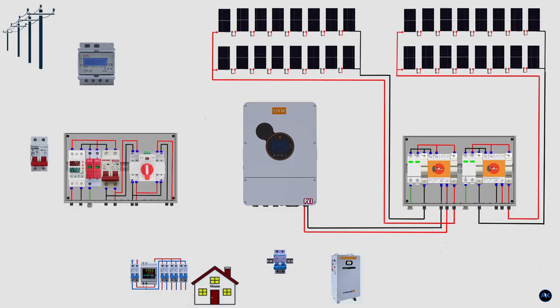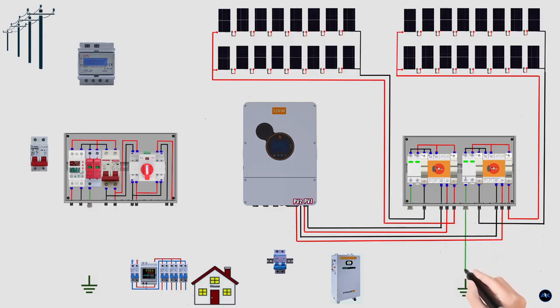After the DC fuses, the cables go into a DC isolator. This isolator allows us to completely shut off solar power for maintenance or emergencies. From the DC isolator, the cables then pass through a DC surge protection device, also called a DC SPD. This protects the inverter from lightning and voltage spikes. Now, the solar DC cables are connected to the PV input terminals of the inverter, matching the correct polarity, positive to positive and negative to negative. Each MPPT input receives its own pair of solar cables.